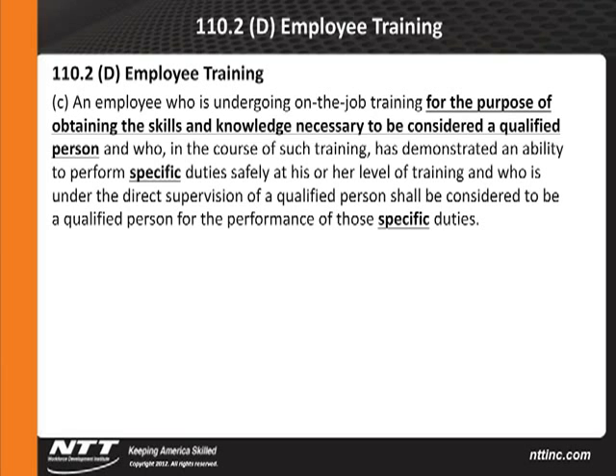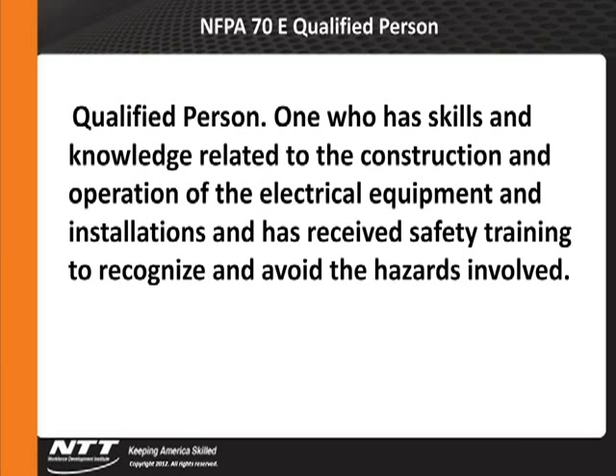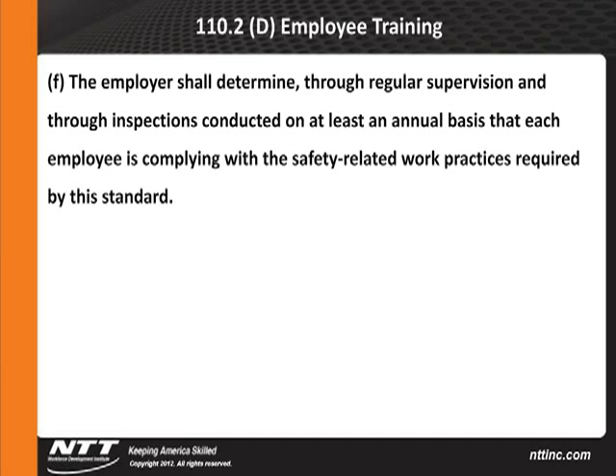So again, more requirements. So what do we got to do then for a qualified person under the standard? One who has skills and knowledge related to the construction and operation of that equipment. Pretty straightforward. So the employer shall then determine on a routine basis, through regular supervision conducted at least on an annual basis, that each employee is complying with the safety-related work practices required by the standard. Ask yourself, what does it mean, regular supervision?